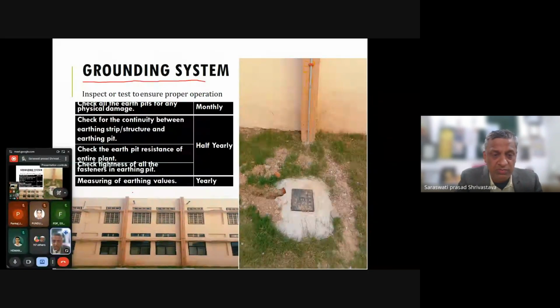This is how the building is covered for this. Check all the earthing pits, which should be around 8 feet deep with copper and salt inside. Check all the pits for any physical damage, and check continuity between earthing and structure strips. This earthing check should be done every 6 months.